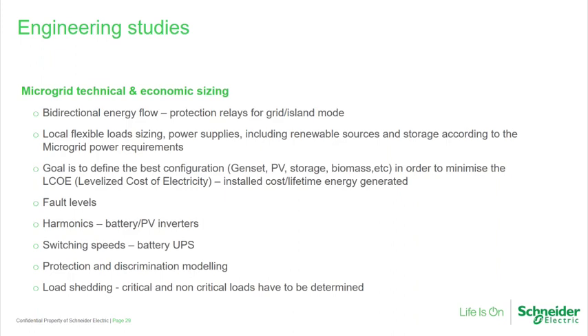So as you're carrying out your commercial modelling, looking at where your finance is coming from, you also need the engineering work—looking at fault levels, your harmonics, your discrimination, derating, and switching speeds with batteries as well. That's quite critical if you're utilising UPS systems.